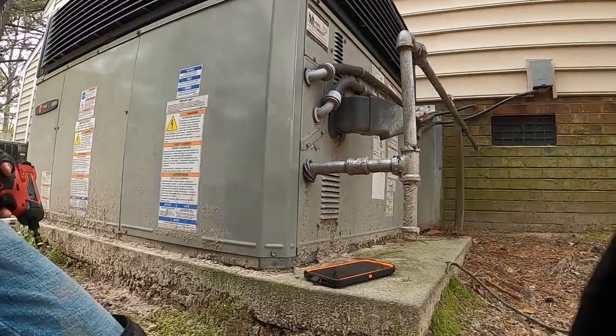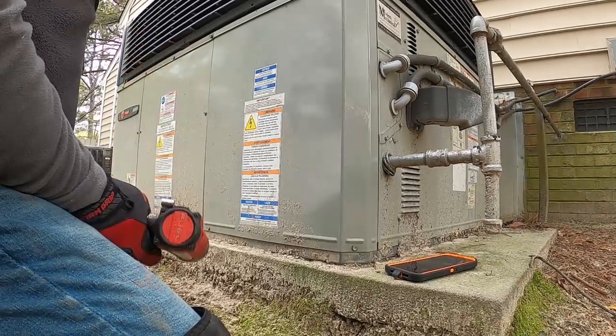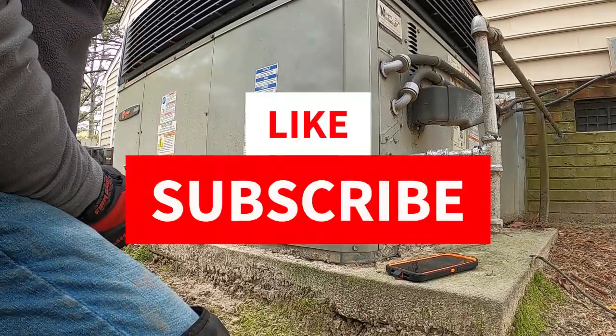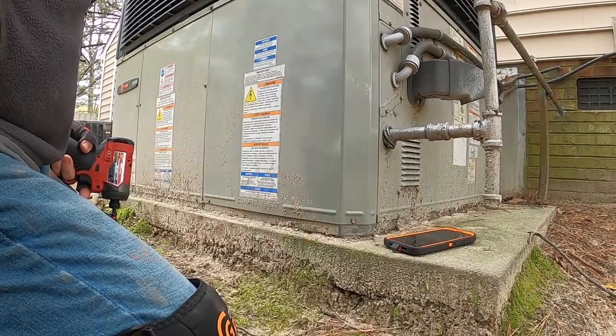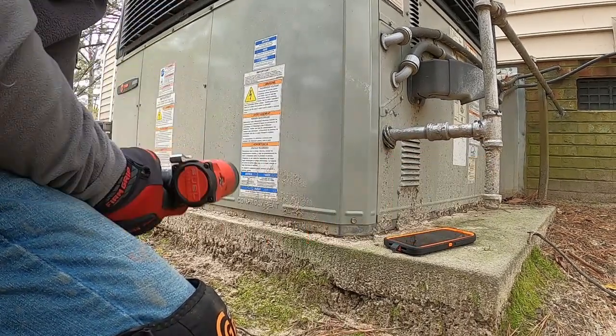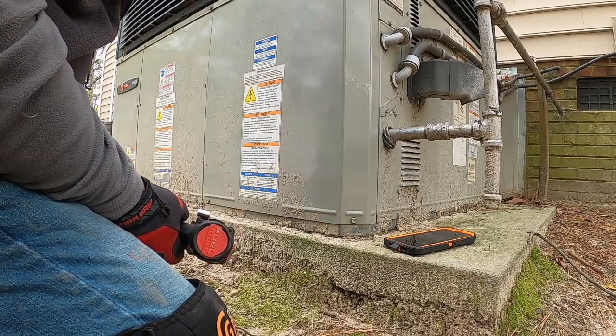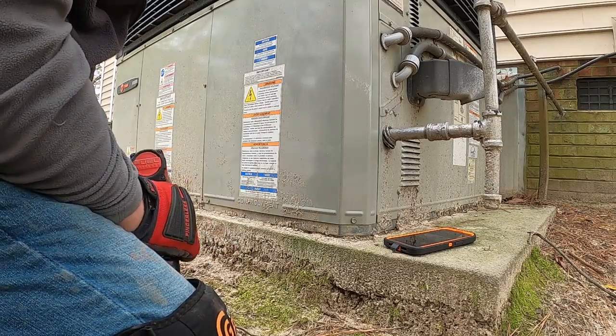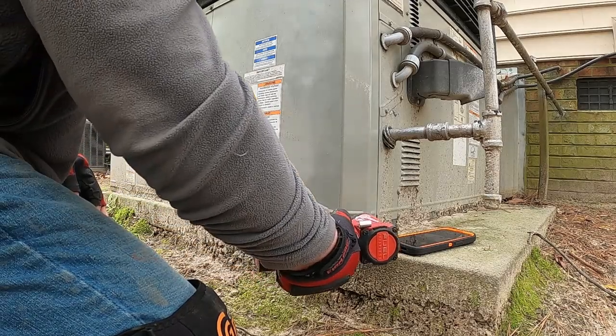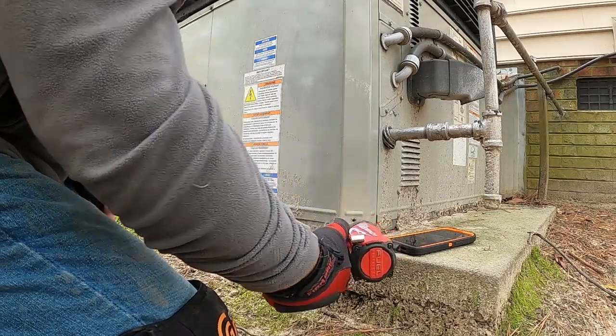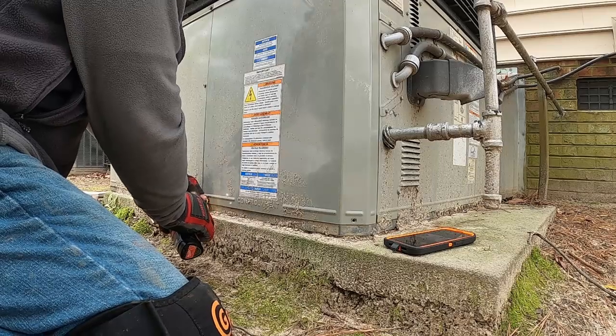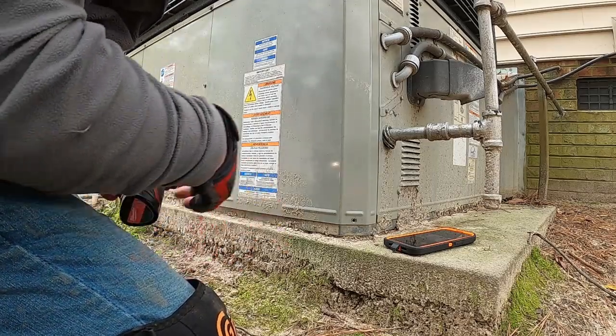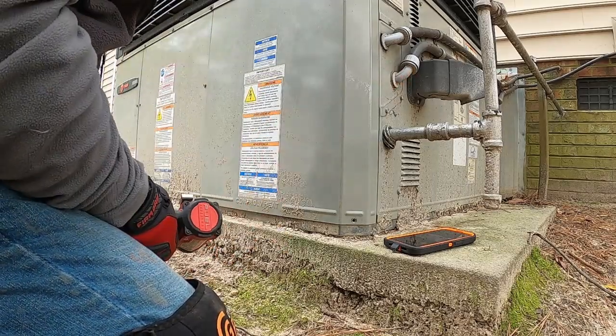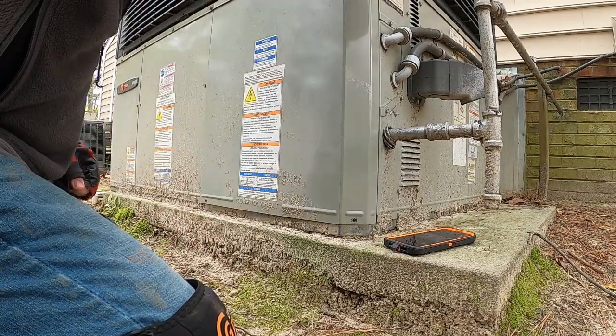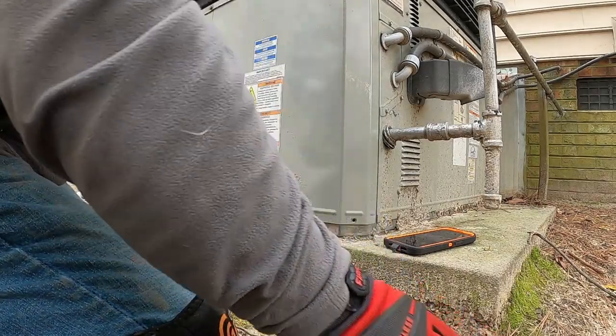Alright guys, we got a no heat call on a Trane package unit, and we'll try to see what we can come up with. Went inside, checked the thermostat in the house. Homeowner replaced his thermostat, thought maybe it was an issue. It is wired right, it is set up right. We do have power, obviously the draft motor's running constantly. So I'm guessing we're on some kind of a lockout.